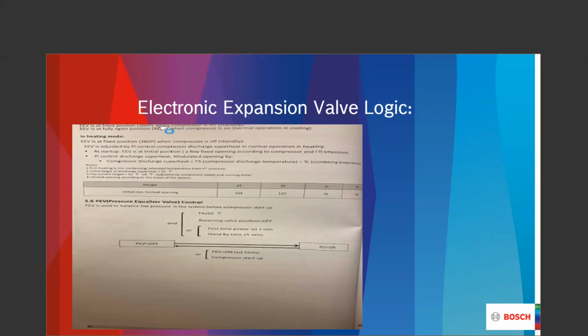So electronic expansion valve, the E valve. Right, I told you earlier that if my E valve is at 360, that's basically its starting place. It can modulate all the way up to the 480 mark. So from 360 to 480. And I literally can push a button and I can see those particular set points. On the 2.0, that button is number 17.